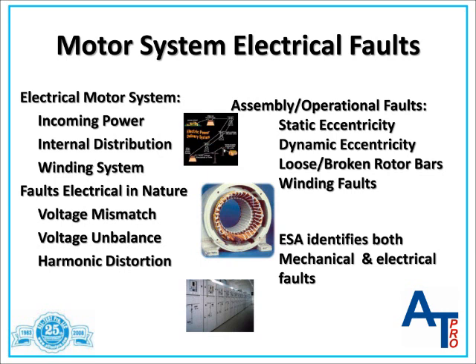Non-sinusoidal input can cause a negative sequencing that creates internal heating. Insulation life reduces by approximately 50% for every 10 degrees C the temperature exceeds its upper limit. Heating of the winding insulation creates winding shorts and grounds. Additional faults in the electrical subsystem can be caused by improper assembly of the rotor stator system, in other words unequal air gaps, loose or broken rotor bars, or eccentric rotor. Since each of these faults affect the motor current, electrical signature analysis identifies these faults even in the very early stages.